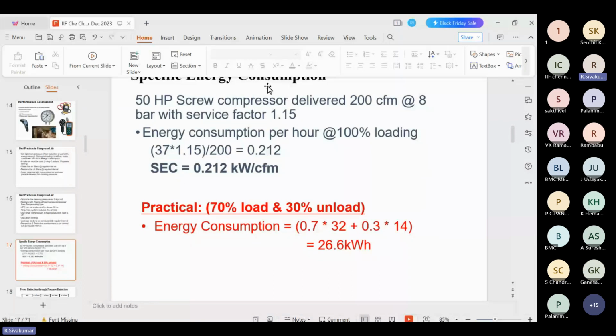We don't have any flow meter mechanism on the compressor in the existing system, so we cannot know how much CFM is generated. Suppose an IoT monitoring device or flow sensor is there, we can monitor how much CFM the compressor generated during this period. Based on that, we can put the CFM value in the denominator, so that 26.6 divided by the CFM value will give the correct benchmarking data. In a later part, we will see how the IoT system helps to monitor the compressor performance.